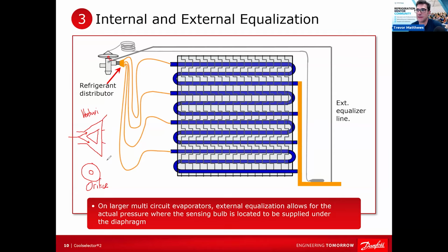Yeah. So, but I think we're just all so amazed by your AutoCAD quality hand drawings that you're doing here, man. So this is a Venturi distributor, like Jamie said, which is a lower pressure drop. I think it's 15 PSI, 20, depending on the manufacturer. And then you have the orifice type, which would go in right here, which you put the block of orifice and it'll be a hole in there. And these can be up to 35 PSI, 20 to 35 PSI, depending on the size of the hole. So that's something you've got to be aware of.